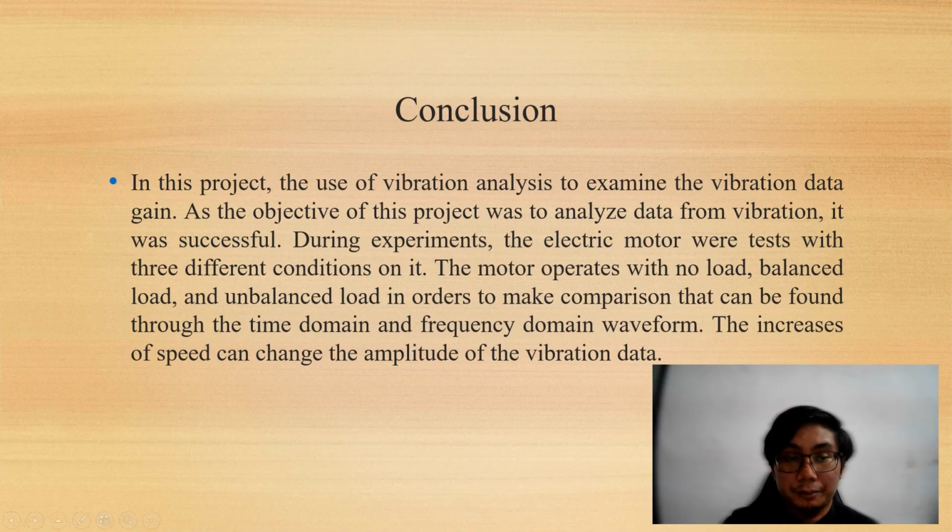For the conclusion, in this project, the use of vibration analysis to examine the vibration data gained, as the objective of this project was to analyze data from vibration, is successfully achieved. During the experiment, the electric motor was tested with 3 different conditions, which is no load, balanced load, and unbalanced load.